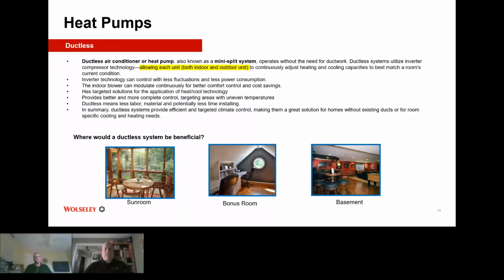A ductless air conditioner or heat pump, also known as a mini split, operates without the need for ductwork. Ductless systems utilize inverter compressor technology, allowing each unit, both indoor and outdoor, to continuously adjust heating and cooling capacities to best match a room's current condition. Inverter technology can control with less fluctuation and less power consumption. The indoor blower can modulate continuously for better comfort control and cost savings. As a targeted solution, it provides better and more complete control, targeting areas with uneven temperatures. Ductless means less labor, less material, and potentially less time installing.